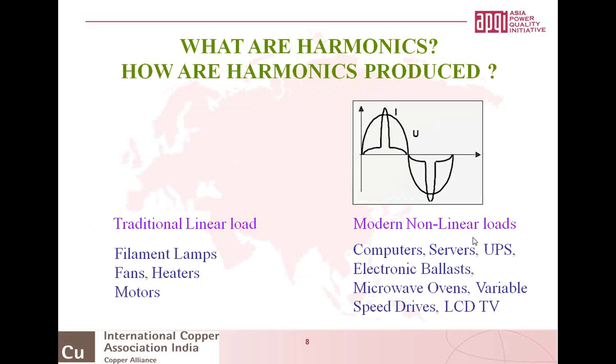Higher losses in transformers, motors, cables, which increases monthly bills; breakdown in CNC machines, which increases production loss; nuisance tripping of breakers, again production loss; overheated cables and terminations leading to production loss; genset failure to start also giving rise to production loss; failed transformer, production loss. Lower power factor will give you a penalty in the tariff, and higher THD will also give you a penalty, as Mr. Srinivas showed in his slide, that some of the electricity boards are already gearing up to levy penalties on consumers who are injecting harmonics into the grid.